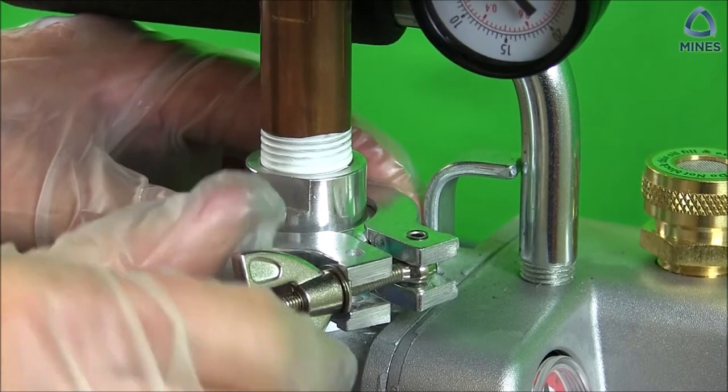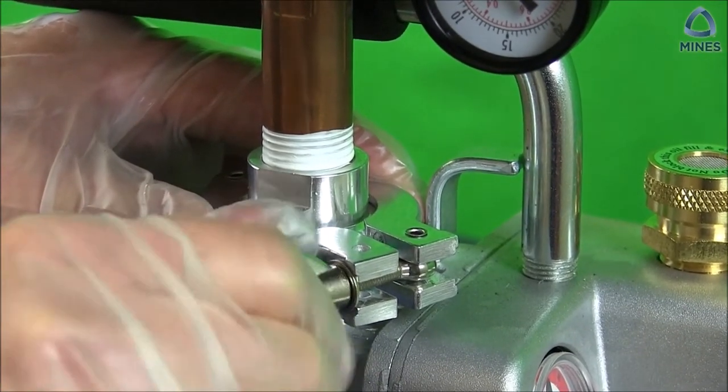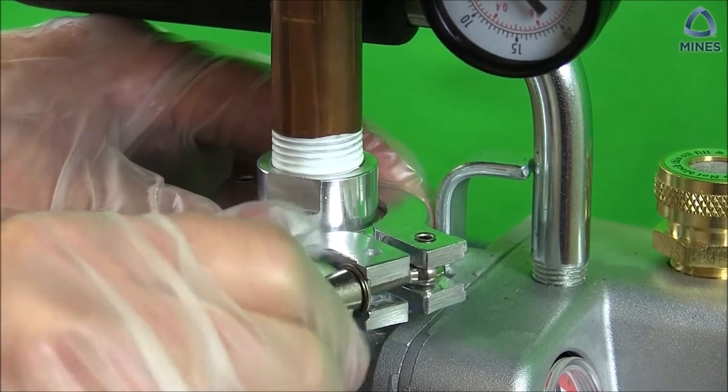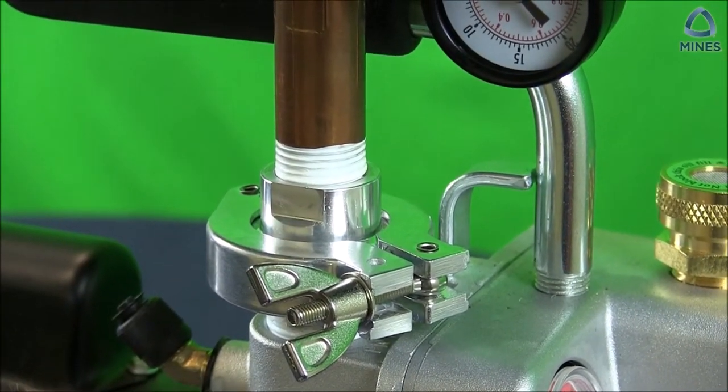However, this suggestion may need to be altered depending upon how the pressure gauge has been mounted on your particular base plate. With the base plate properly positioned, tighten the wing nut by hand until it's reasonably tight. It's not recommended to use a tool for this purpose because a snug hand tightening should be sufficient to form a good vacuum seal between the O-ring and the two NW flanges.